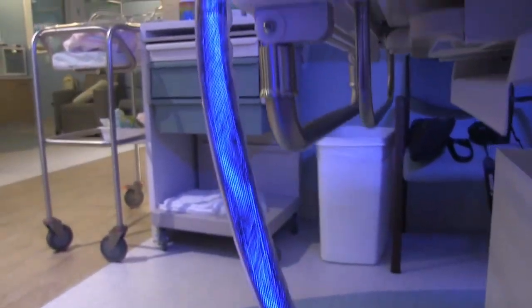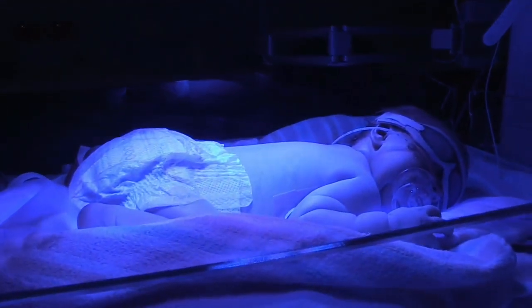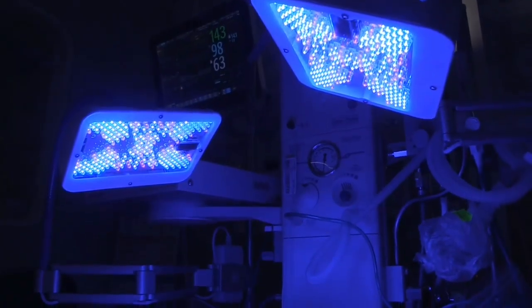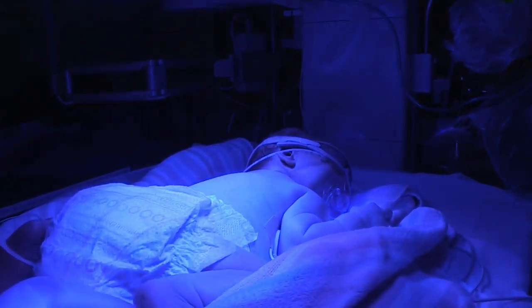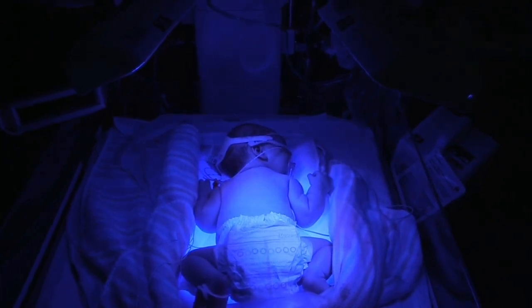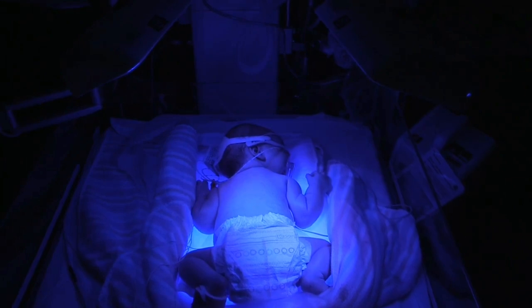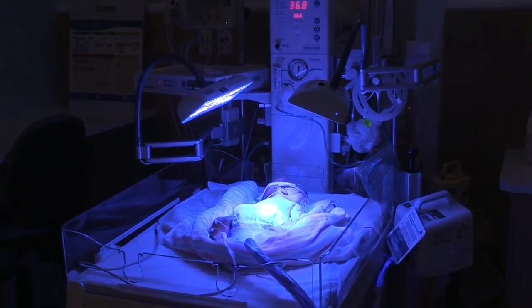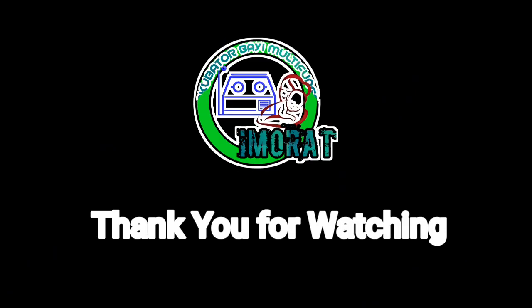We conclude that the ESP32-based multi-function infant incubator is appropriate to be utilized in hospitals and primary healthcare services that use manual monitoring. Besides long-distance monitoring, the infant incubator is equipped with phototherapy and a mechanical swing to calm the baby when crying. At temperatures above 35°C and RH below 40%, four light bulbs turn off and the fan turns on to minimize temperature increase. We hope this technological innovation can improve the quality of health services in Indonesia, especially by reducing infant mortality. Technology doesn't replace people — it enables people.